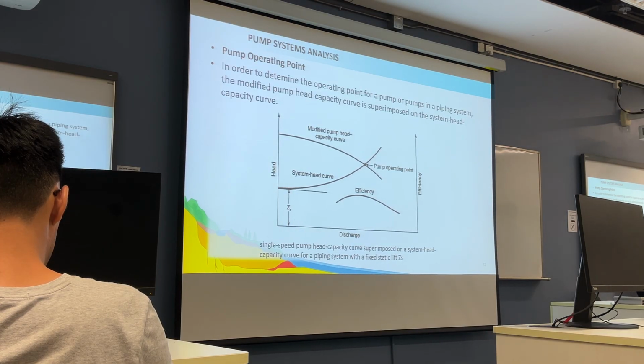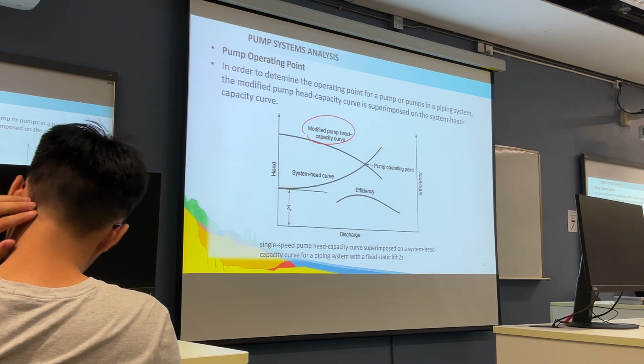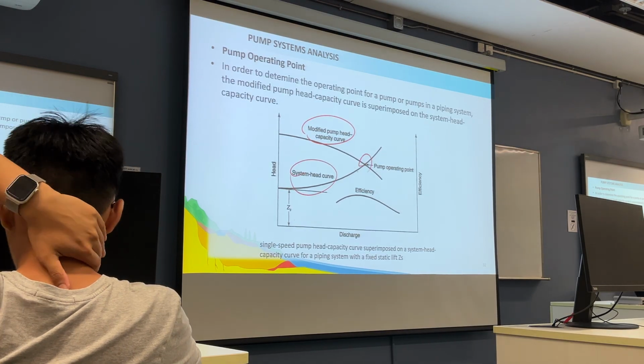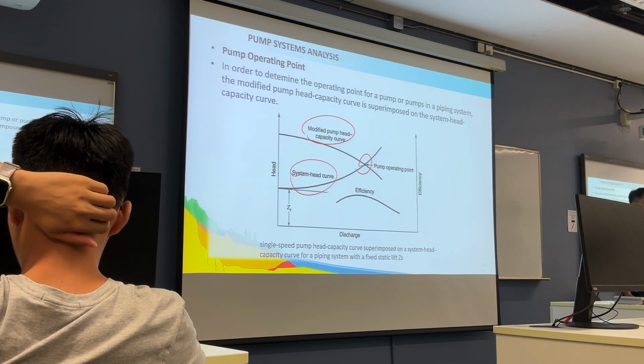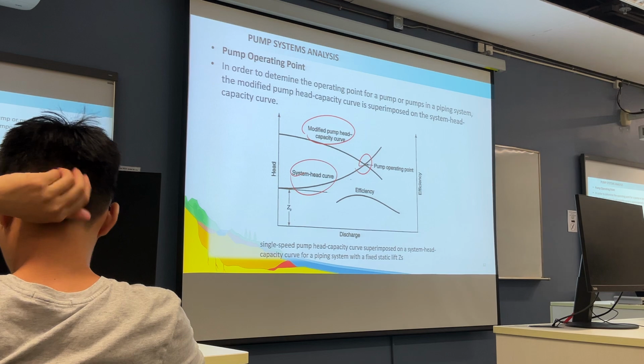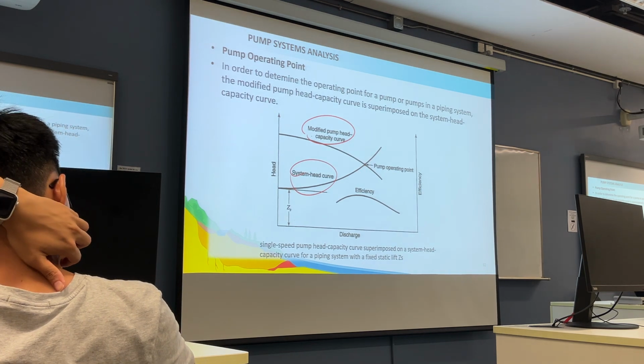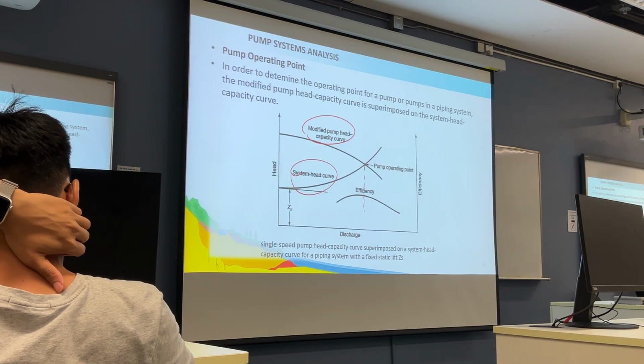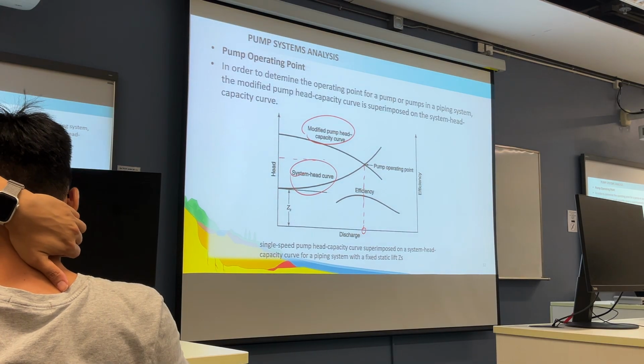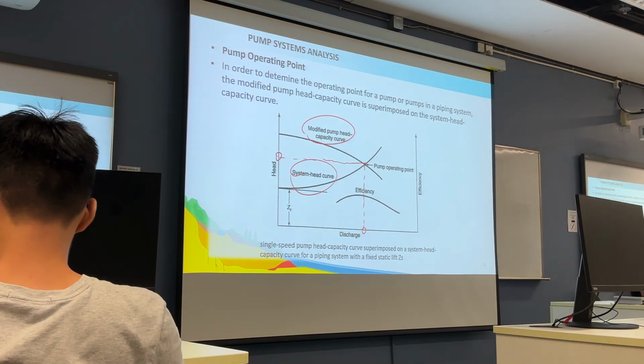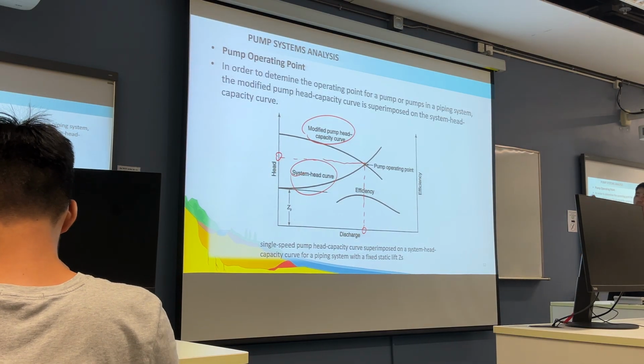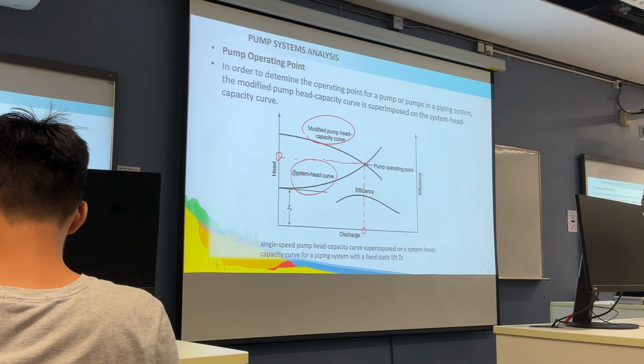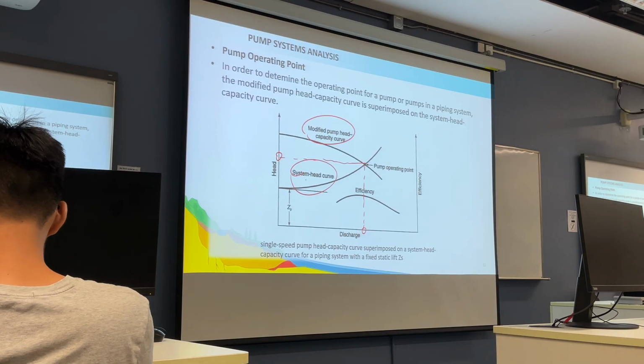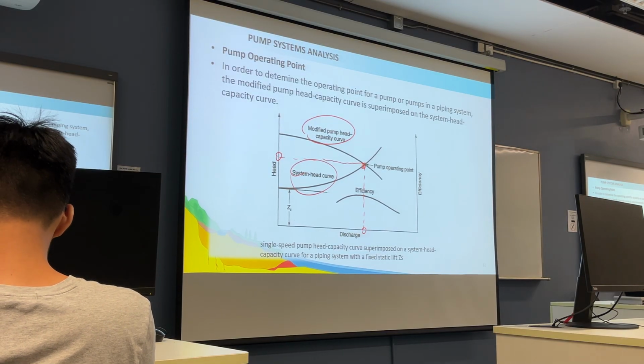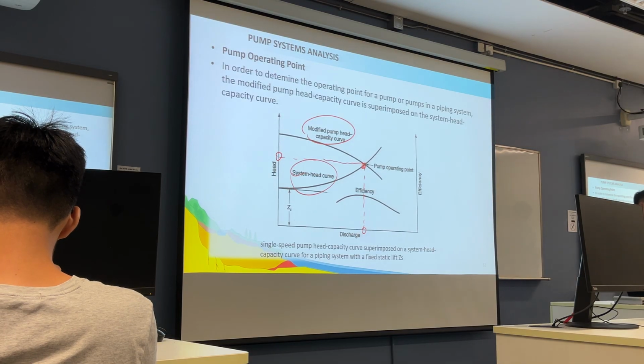So the thing is, we need to combine the pump curve and the system curve to find the intersection, to find the system operating point. The system operating point indicates that when you apply this pump in this system, it will work at the discharge here and the head here, okay? Because we know the pump can provide a head range like this and a discharge range as here, but if you apply it to this system, the pump working status is known, or can be determined, just like this.